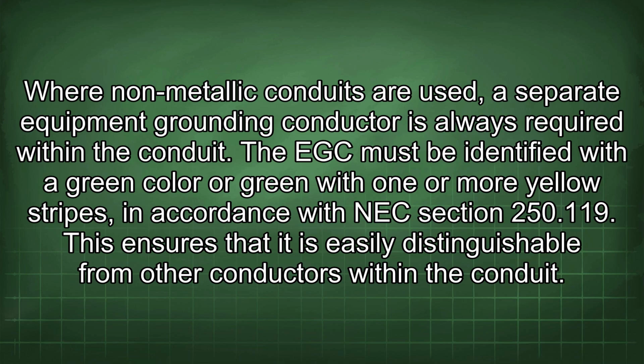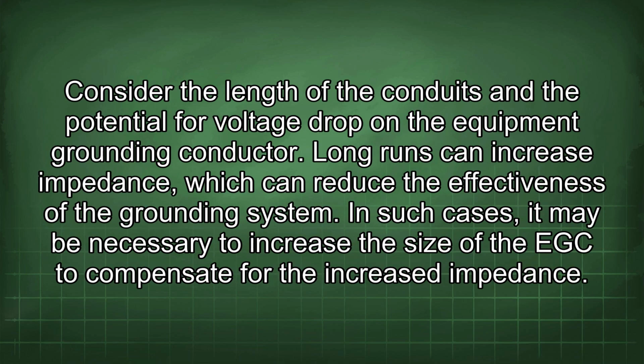The EGC must be identified with a green color or green with one or more yellow stripes, in accordance with NEC section 250.119. This ensures that it is easily distinguishable from other conductors within the conduit. Consider the length of the conduits and the potential for voltage drop on the equipment grounding conductor. Long runs can increase impedance, which can reduce the effectiveness of the grounding system. In such cases, it may be necessary to increase the size of the EGC to compensate for the increased impedance.